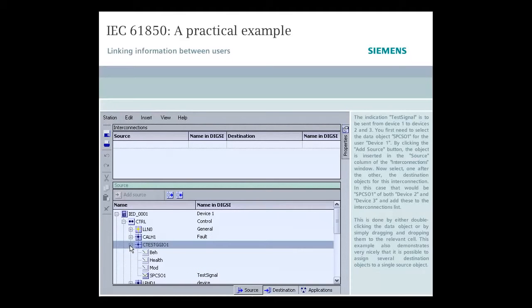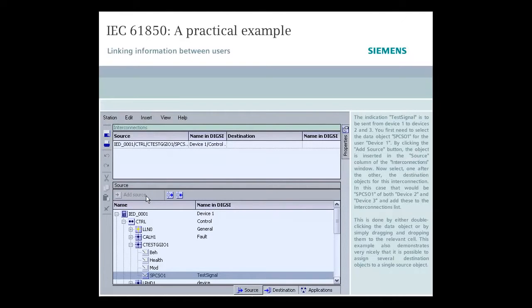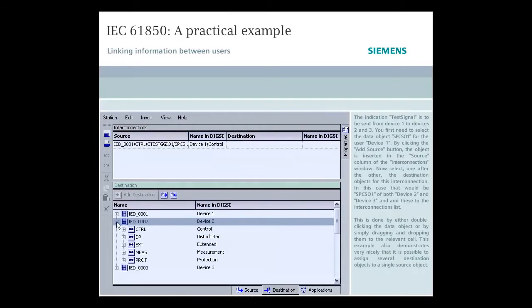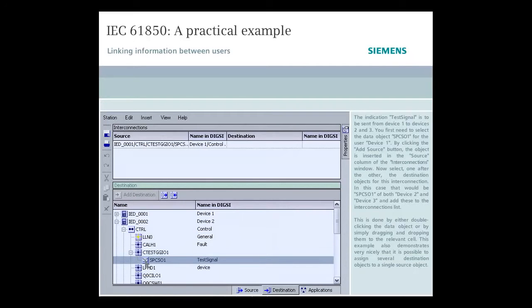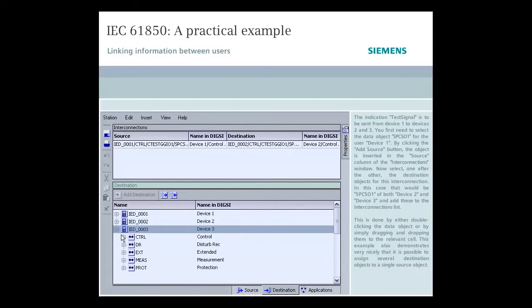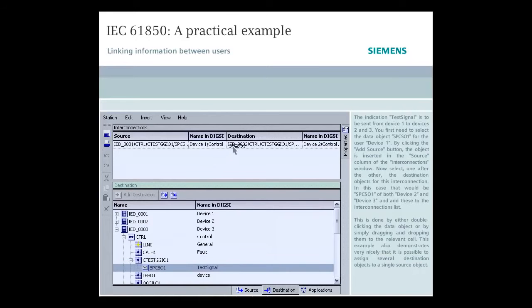The indication Test signal is to be sent from Device 1 to Devices 2 and 3. You first need to select the data object SPCSO1 for the user Device 1. By clicking the Add Source button, the object is inserted in the Source column of the Interconnections window. Now select one after the other, the destination objects for this interconnection. In this case, that would be SPCSO1 of both Device 2 and Device 3, and add these to the Interconnections list. This is done by either double-clicking the data object, or by simply dragging and dropping them to the relevant cell. This example also demonstrates very nicely that it's possible to assign several destination objects to a single source object.